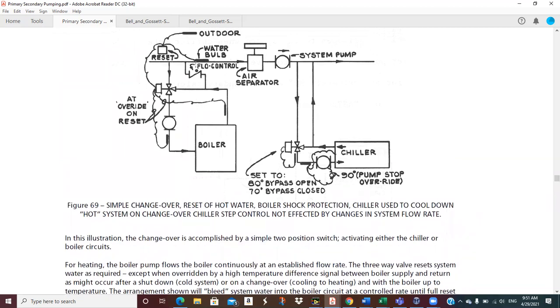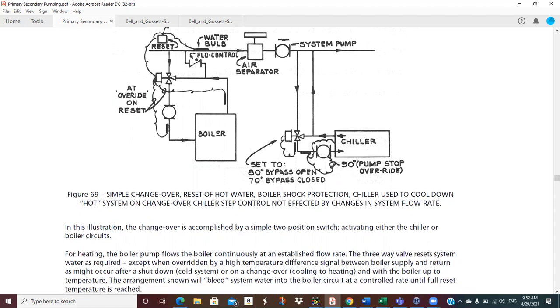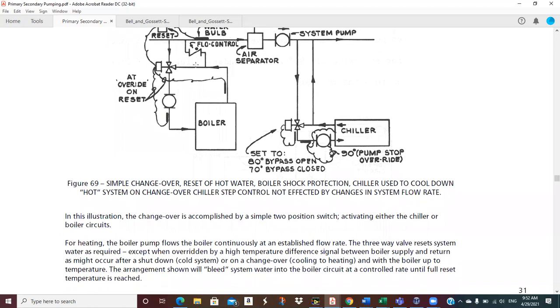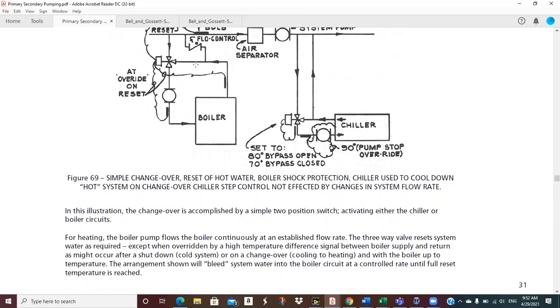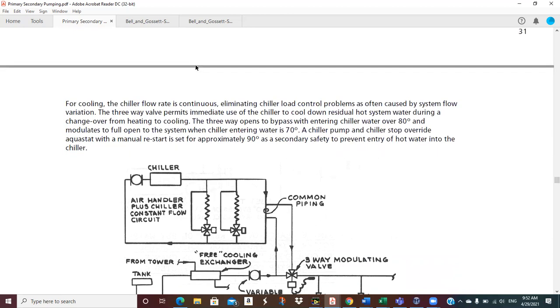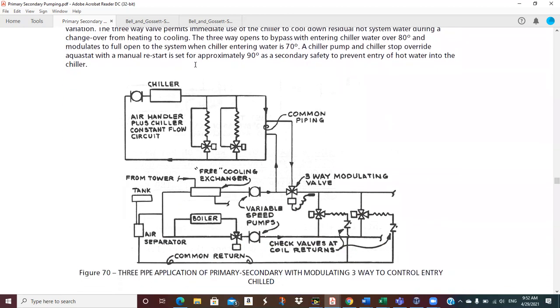Okay, the three-way valve resets system water as required with outside air temperature, except when overridden by a high temperature differential signal between the boiler supply and return, which might be after we've been on the chiller and we got cold water and we don't want to shock that boiler. So we're going to protect it. So you've got some protection, and the same sort of thing is going on with the chiller. You can read that, and then three-way pipe.